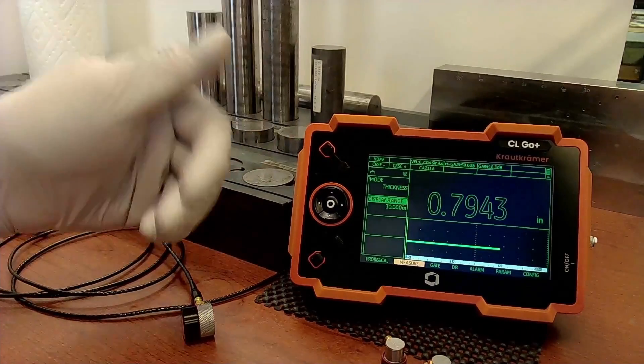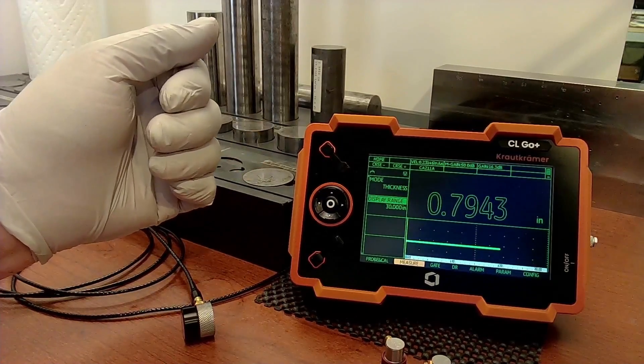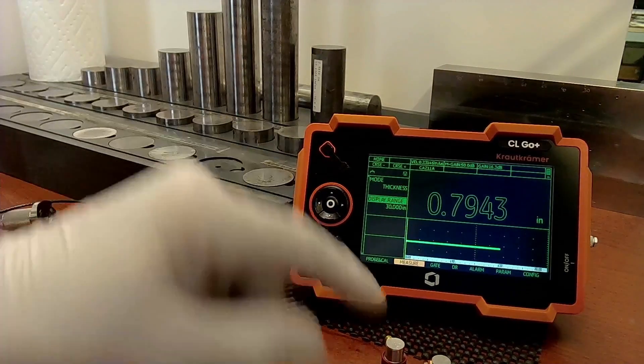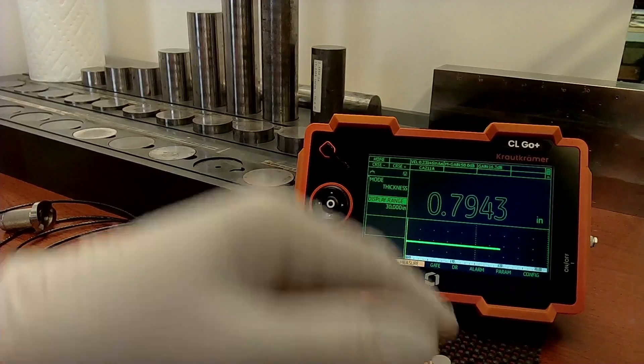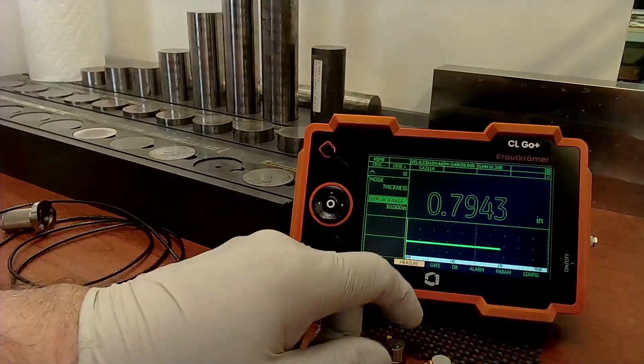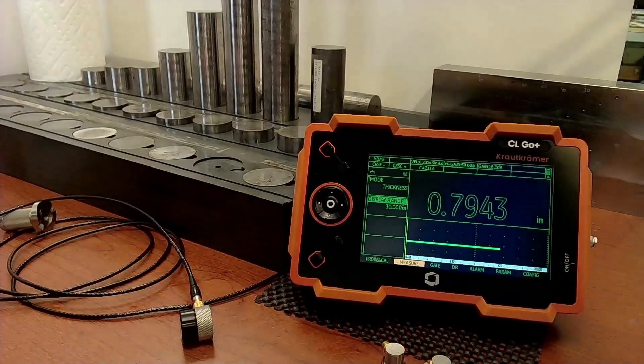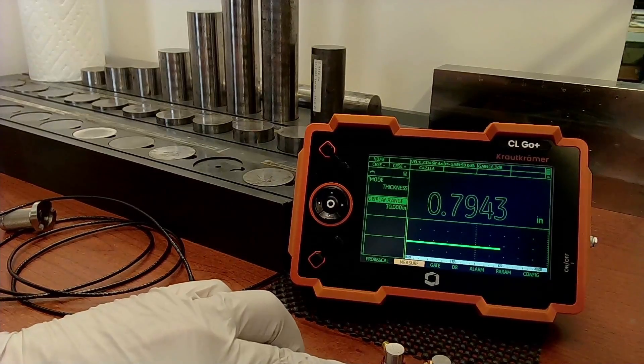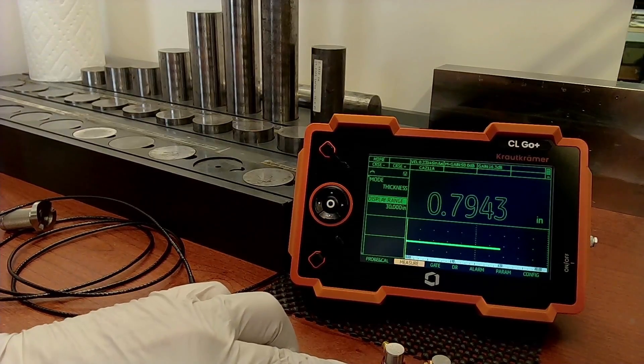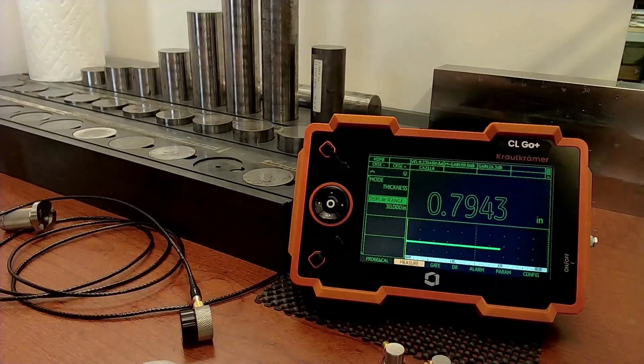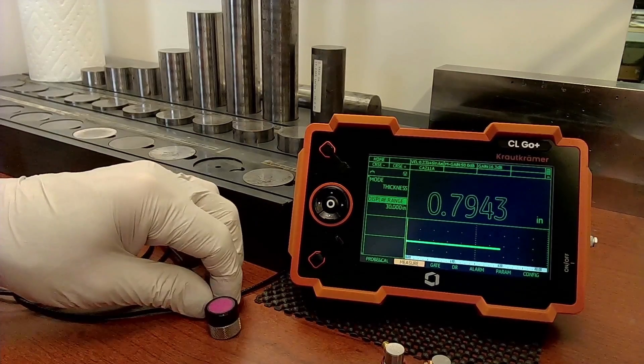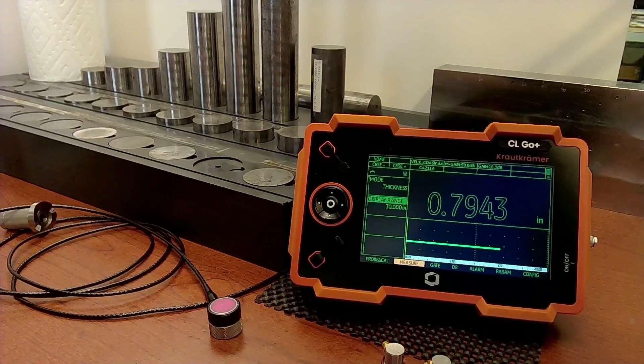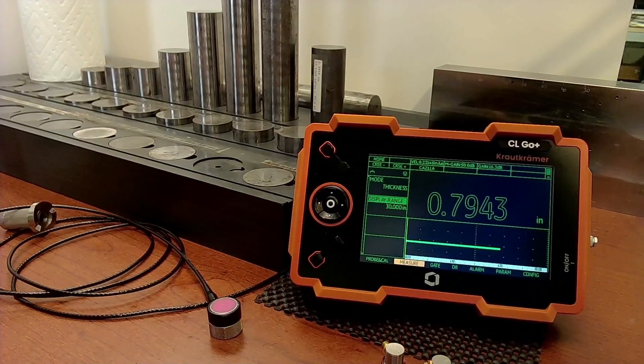Just select a probe. Run through the calibration process that's appropriate for that probe. Again, the direct contact probes will use the zero block. Delay tip probe. The Alpha 2 DFR uses interface start mode on the delay tip. So we don't need to zero that probe. All we need is one sample for velocity. And the instrument is calibrated.